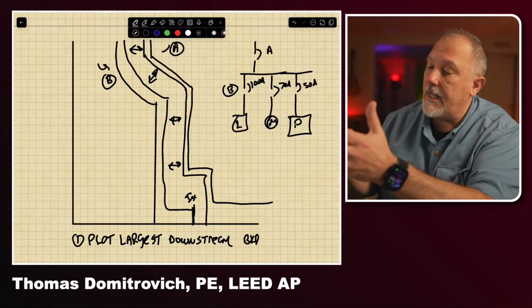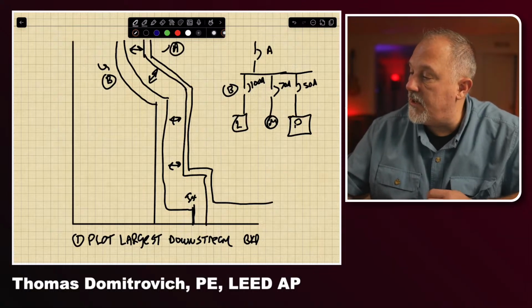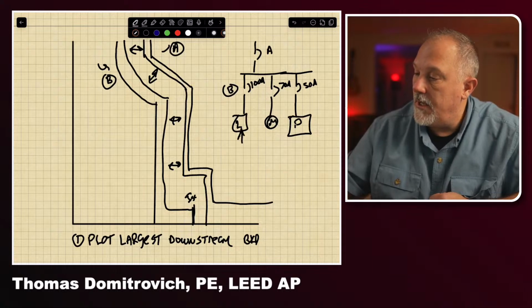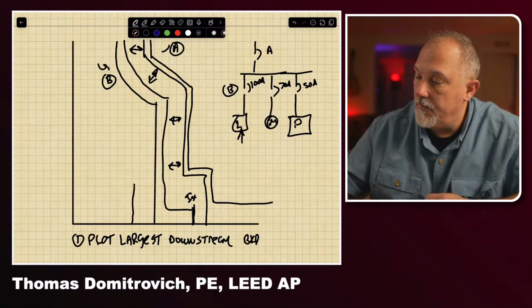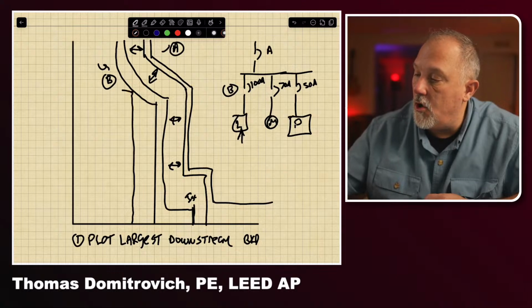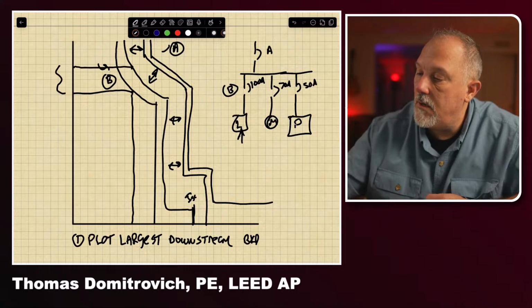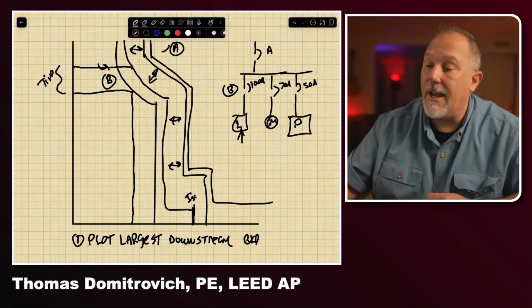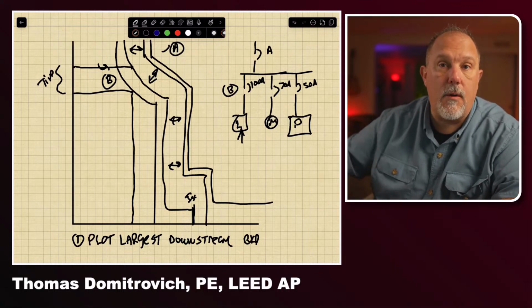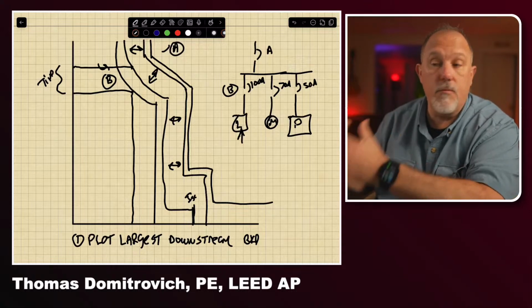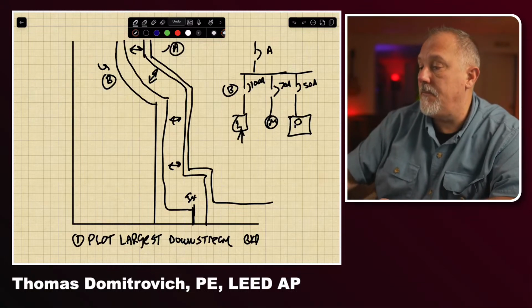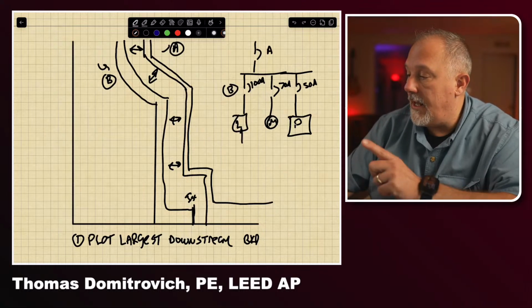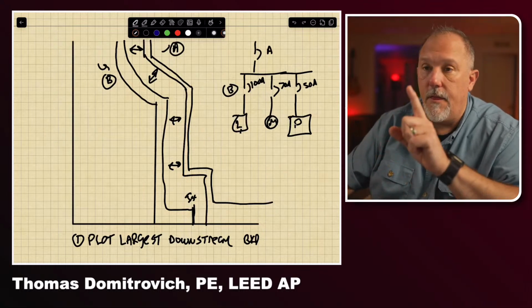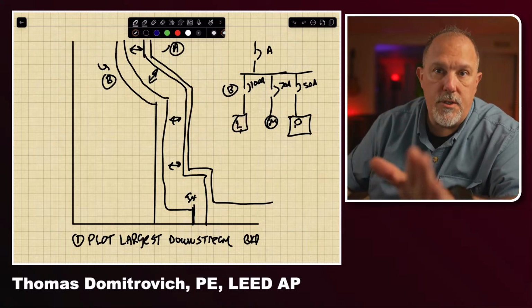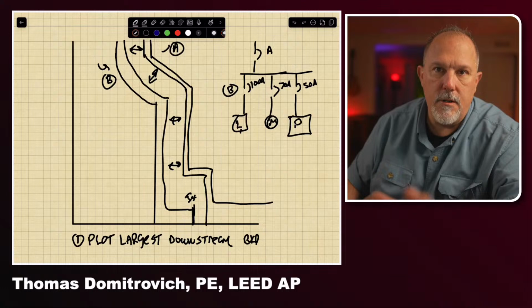And I can have an overload, so if downstream of B, if I add too much lighting load, I'm going to open device B anywhere between those two times, and I'm not going to open device A. So I have coordination in the overload region, right? So regardless of my loads, I have coordination.